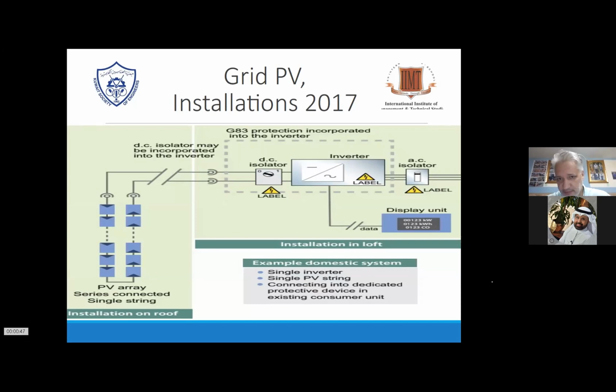So when you go for a central grid inverter, it will not isolate certain areas, and if, for example, they're shaded, it will just overrule them. If the shading gets too much, the central grid inverter will go off the perfect values and actually derate the other strings to a certain extent. So when you go to the sites during an installation, it's always best to leave the shaded areas off, or they only shade in winter time, or maybe 1 hour or less in the daytime.